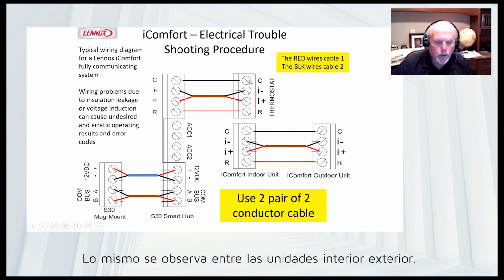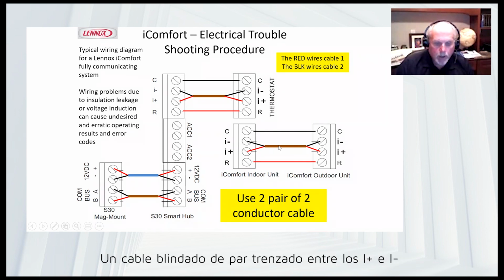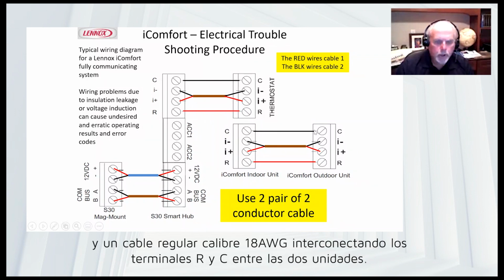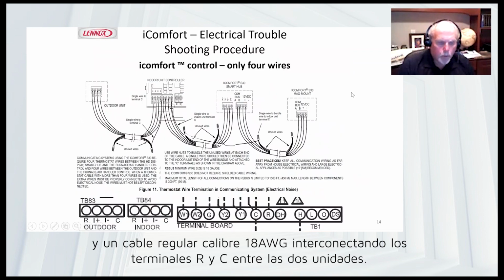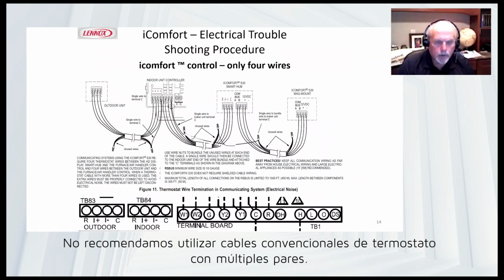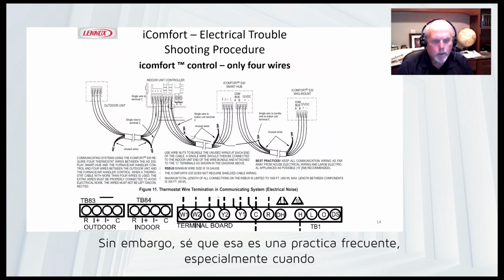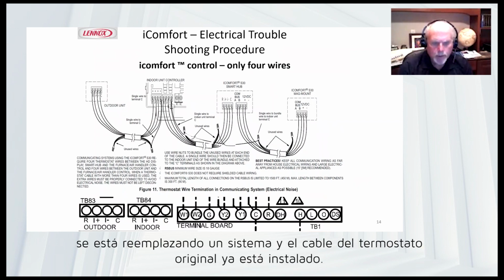And the same going from the indoor unit to the outdoor unit. All right, we have shielded twisted pair wire for the communication bus, I plus, I minus, and we have one 18 gauge two conductor cable for R and C. Regular thermostat wire where you have multi-conductors in one cable is not recommended. However, I do know that that is used quite a bit out in the field, especially when you are replacing a system that already has thermostat wire there. Sometimes you do have multi-conductor wire.